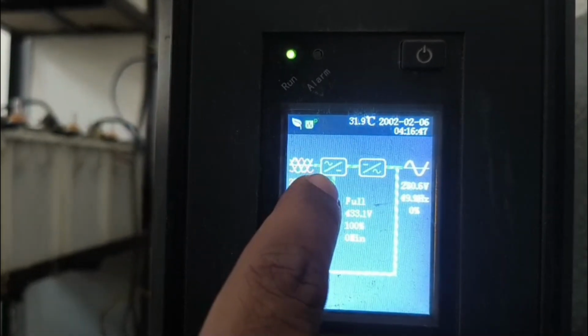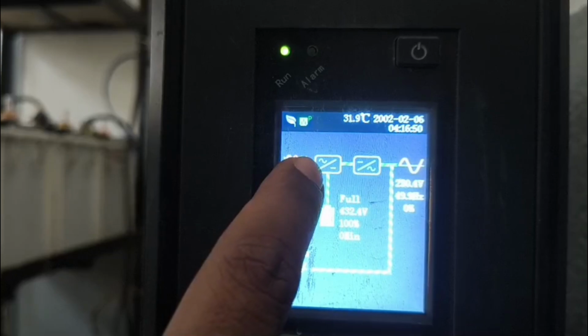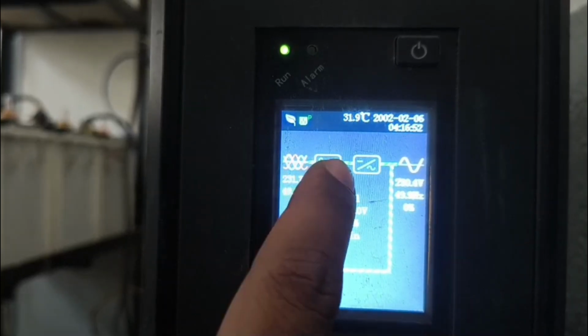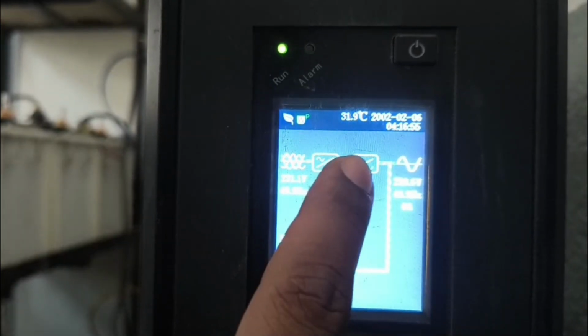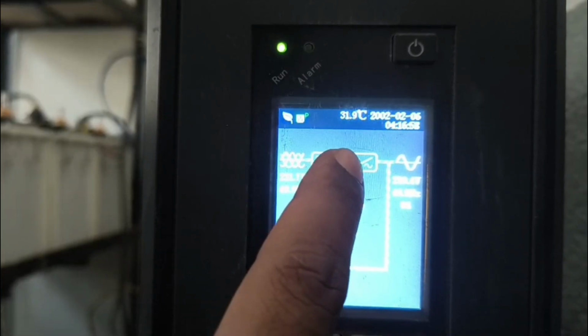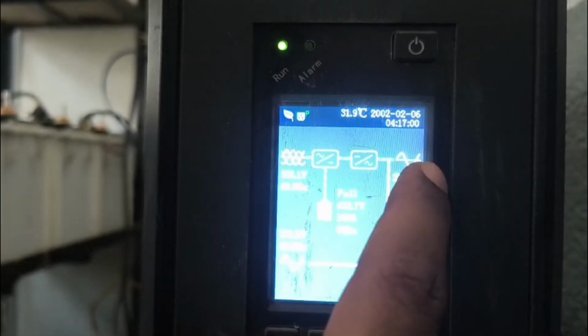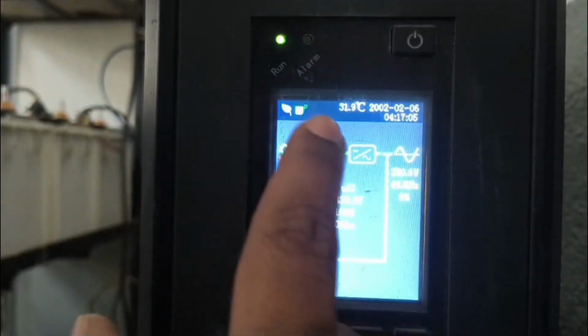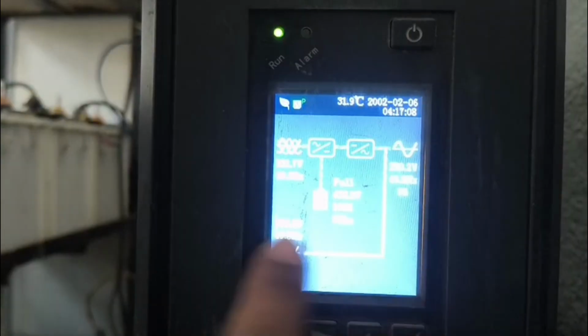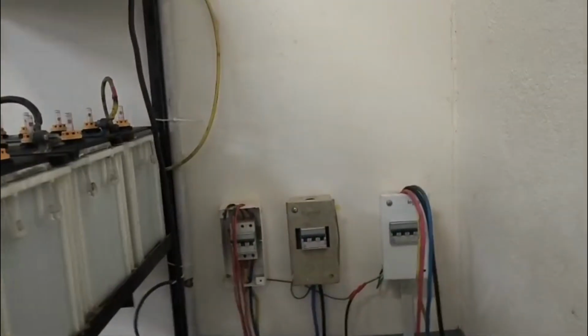Now you can see the 230 volt input is available, and it is feeding the batteries and also the load. The first operation is a rectifying operation. The AC is rectified into DC. It is fed to the battery and also to the load. Before the load we have an inverter operation. In the inverting operation, the DC is converted into AC and fed into the load, and we have a special bypass arrangement. When the inverter is being serviced, we can bypass the supply to the load. Okay, so I will give you these schemes over here.